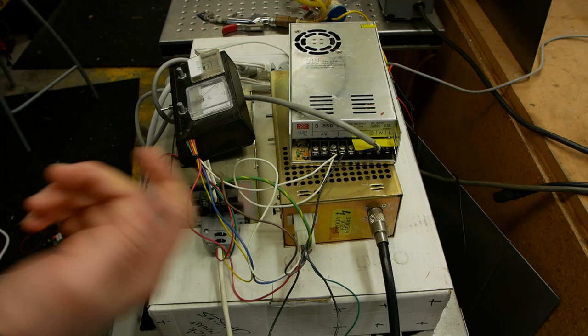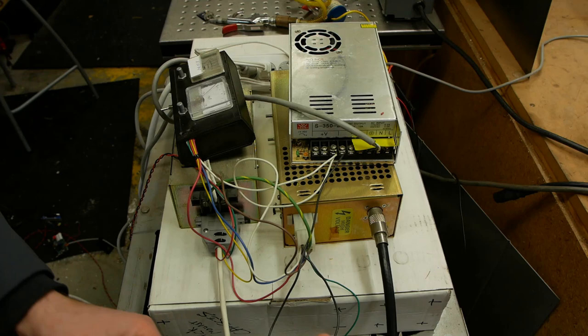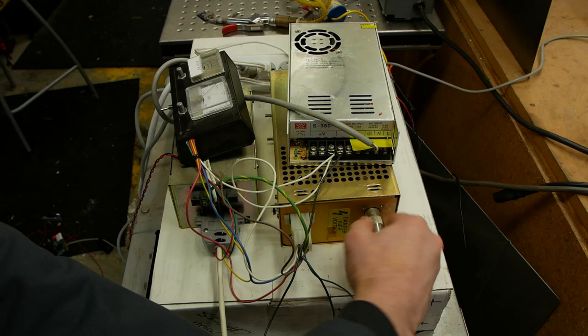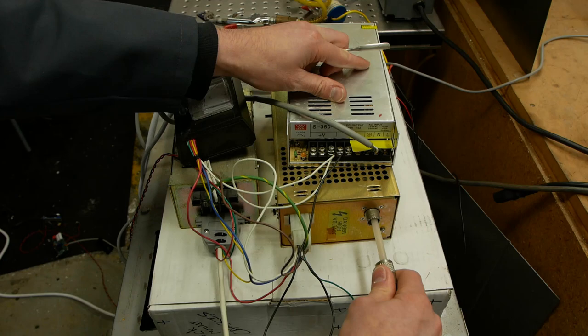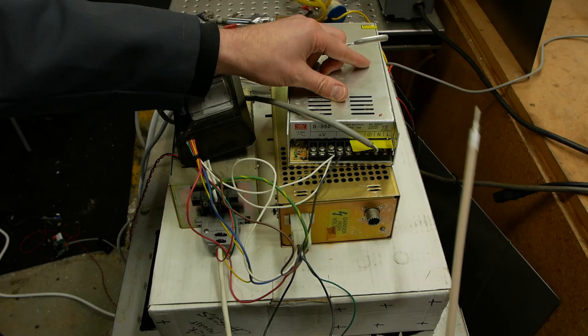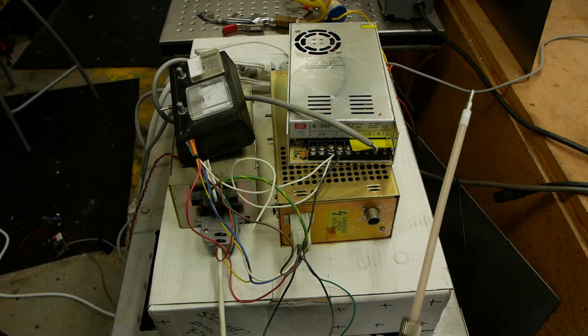This is kind of funny too. It looks like these high voltage connections are shielded. Remember, because if you've got 50,000 volts in a wire, it's gonna charge up things nearby and draw dust to it and create all kinds of problems within the field. So it's actually a coax, but this is no ordinary PL259. In fact, whoa, it's a very strange looking connector there. Obviously meant to just keep down arcing and stuff, although this one seems a little excessively long. I thought you'd get a kick out of that.